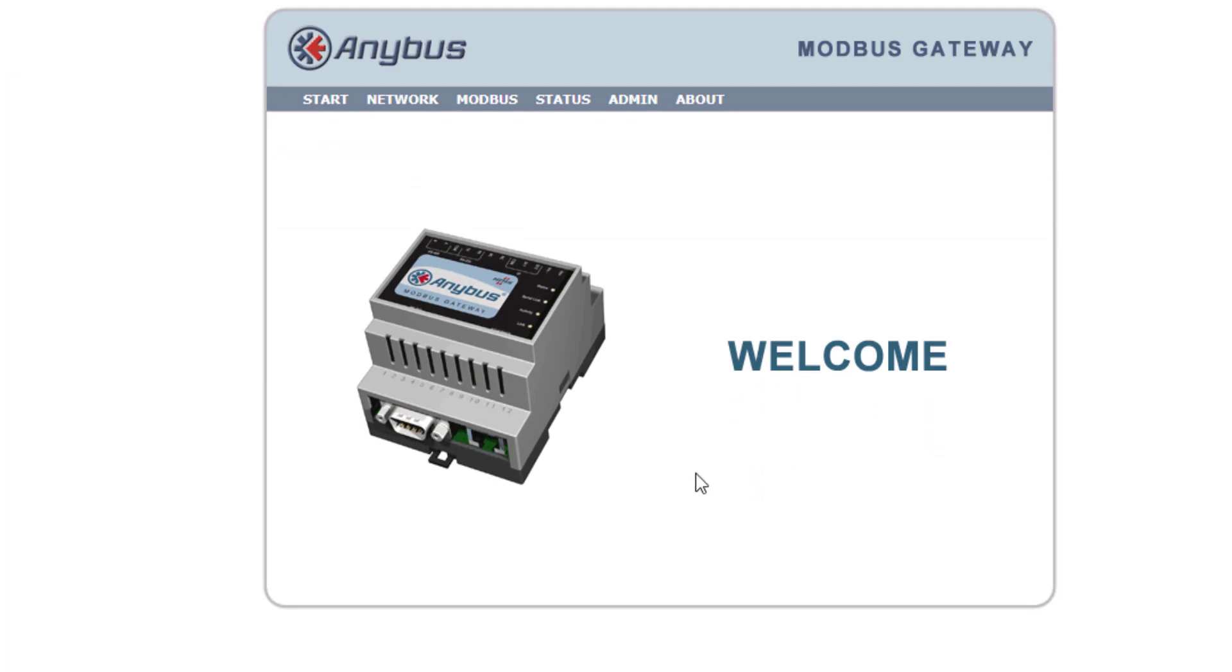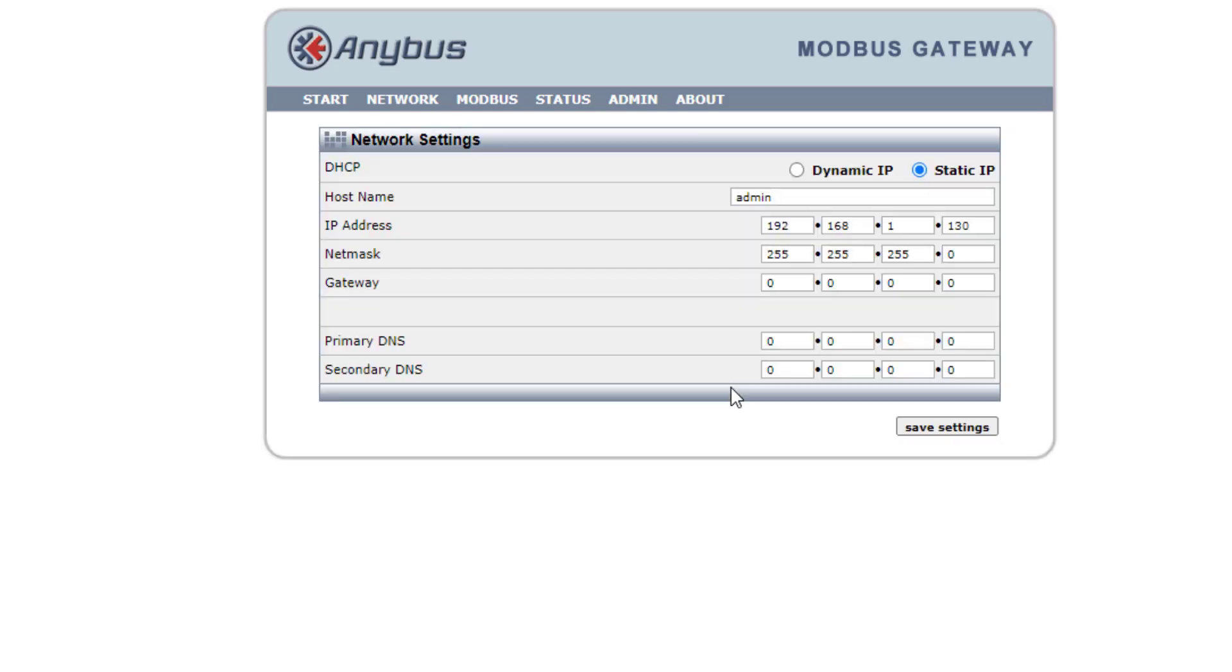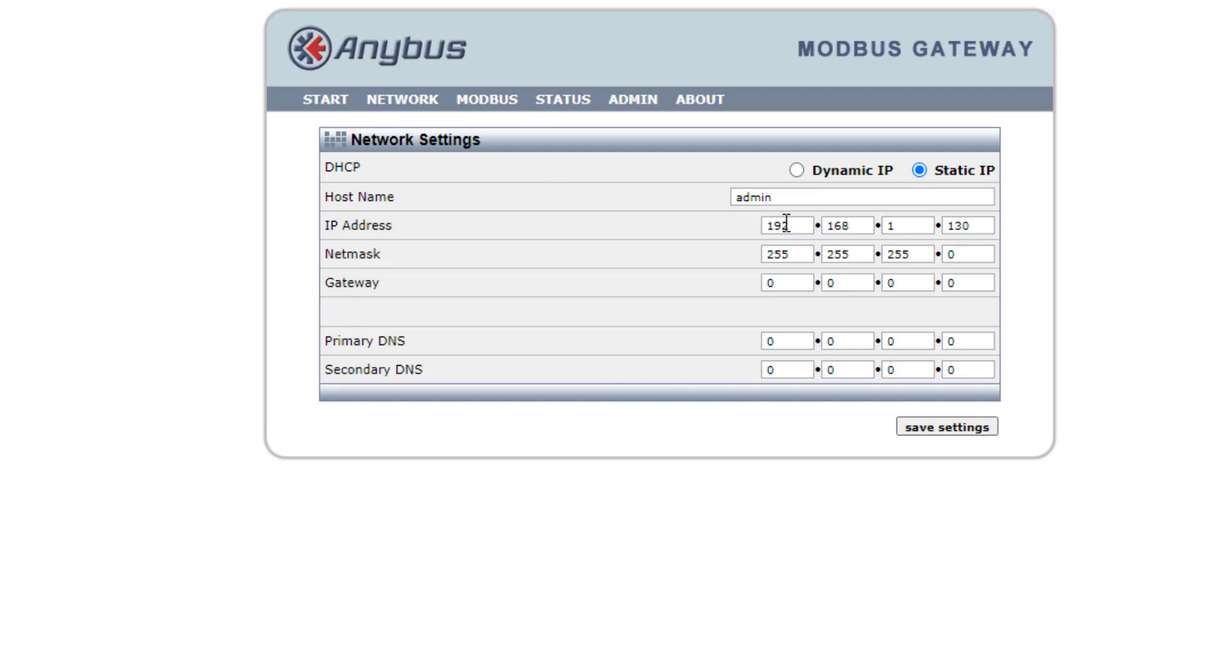First thing we need to do is we have a look at our network, which is the Modbus TCP side of the device. Because we're looking at automation, we want to assign a static IP address because our PLC is going to be talking to this at some point. So we don't want dynamic just in case. Then we have our IP address and our Netmask. The serial converter that we're using won't let you put in a gateway.